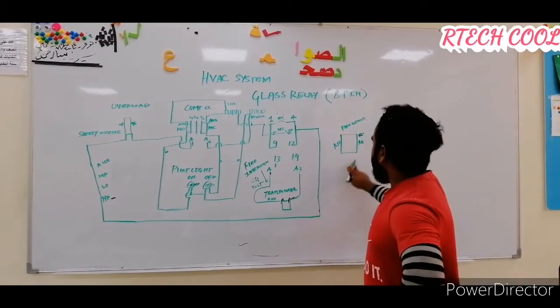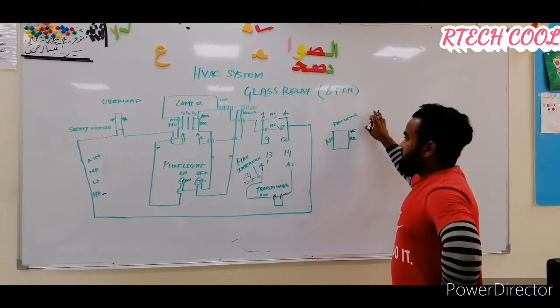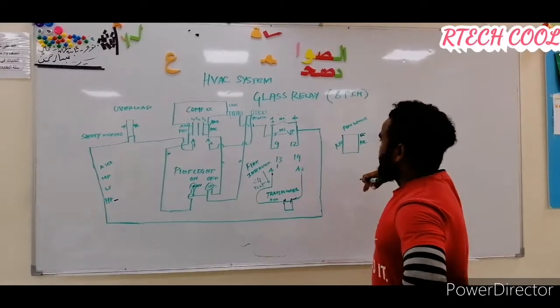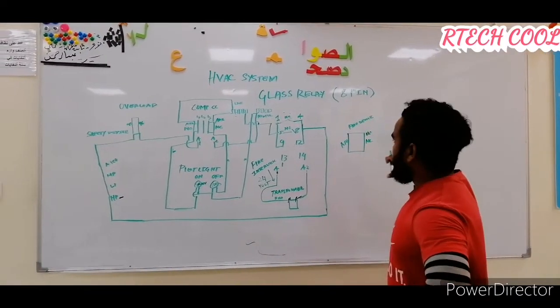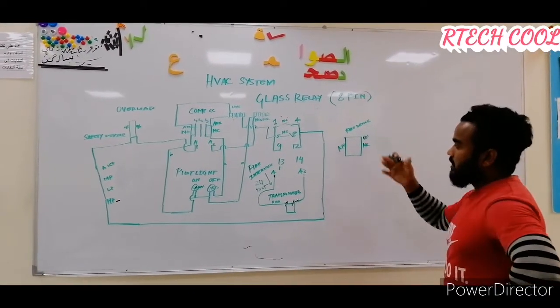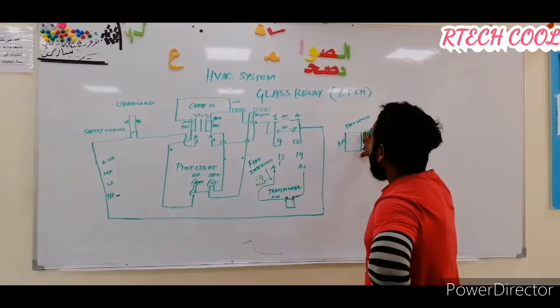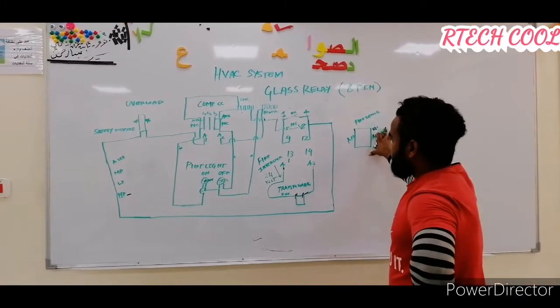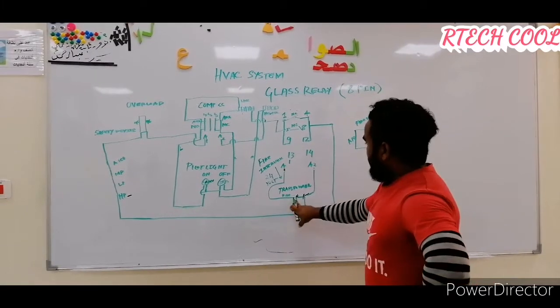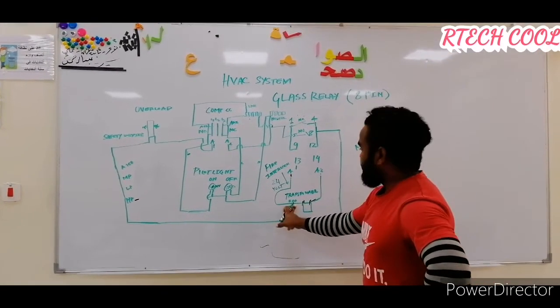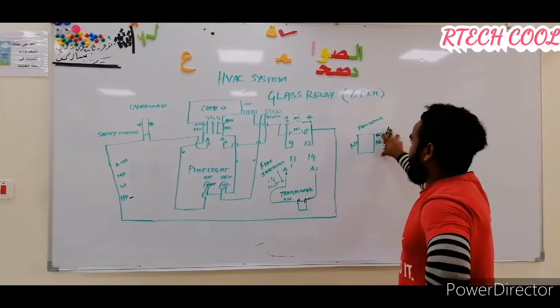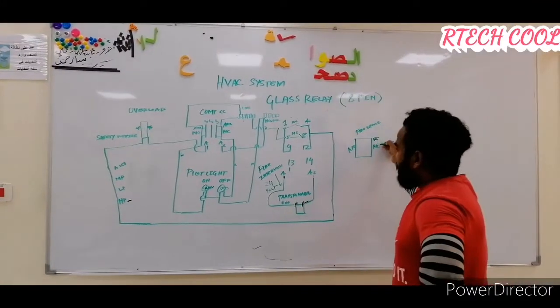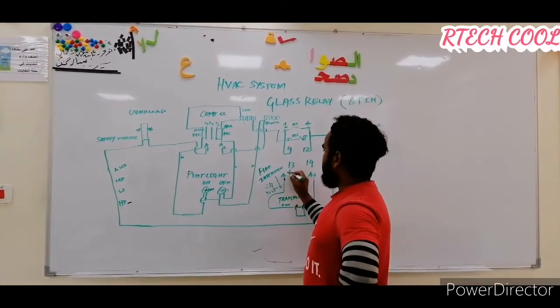This wire comes from the NC point to the fire interlock device. There is a fire interlock device inside the building area — inside the house, shopping complex, mall, school — wherever our unit is. This device connects from our 24V line voltage through its NC point. Since NC means always closed, the current always flows through it normally.